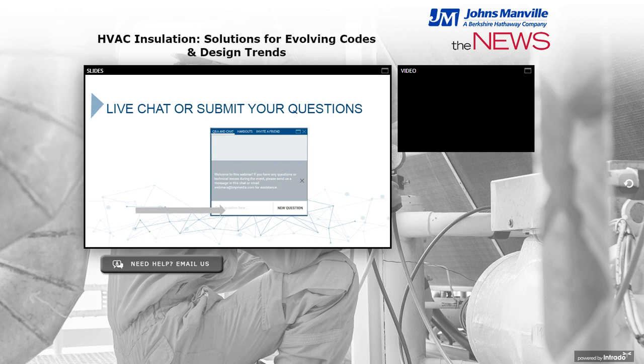Sure, that's a great question—we get asked a lot about that relative to duct liner. The standards for bringing together sections or seams of duct liner say it needs to be neatly butted, coming as close as possible, touching at the very least. I was always taught that insulation should touch at the transverse joints where you're bringing them together, if at all possible. The one thing to remember about duct liner is that its main purpose, the number one reason you use it, is acoustical control.